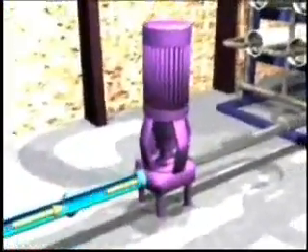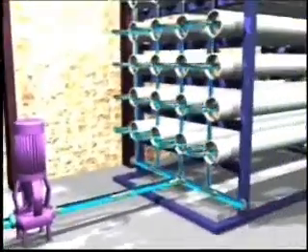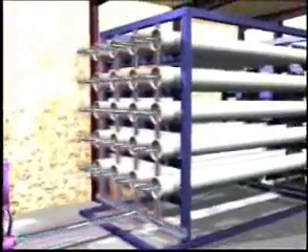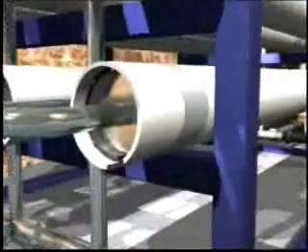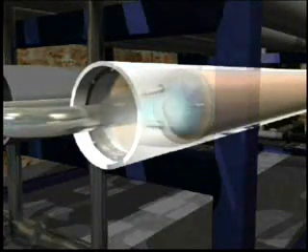The pre-treated water is then pressurized by pumps up to approximately 1,000 pounds per square inch and sent to the reverse osmosis device. The water is then distributed to an array of reverse osmosis modules.